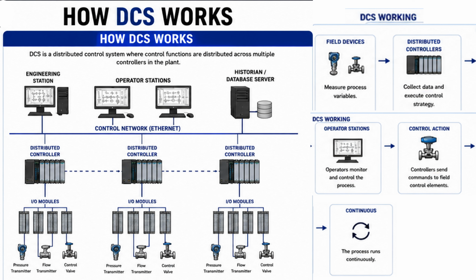Why distribution matters. Imagine one controller suddenly fails. In a traditional centralized system, the entire process may stop. But in a DCS, only one small section is affected. The remaining controllers continue operating normally. This is one of the biggest advantages of DCS. Higher availability. Higher reliability. Less production downtime. For industries where every minute of shutdown costs thousands of dollars, this advantage is extremely valuable.